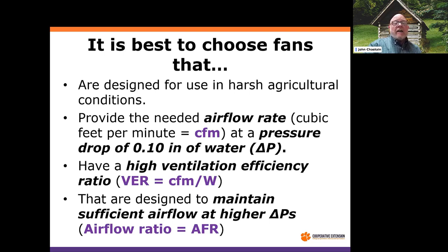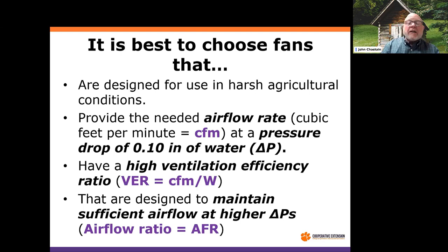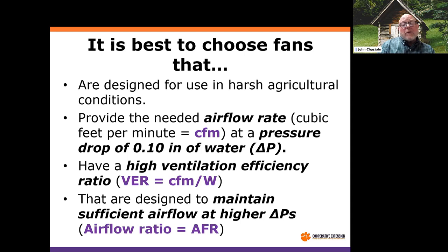The next important thing is efficiency, and we want a high ventilation efficiency ratio — I'll abbreviate that as VER — which is basically the CFM you get for every watt of input power. That's a major piece of the efficiency picture. The last criterion has to do with overall fan design: we want a fan designed to maintain sufficient airflow as it works at higher pressure drops, and we call that the airflow ratio, or AFR.